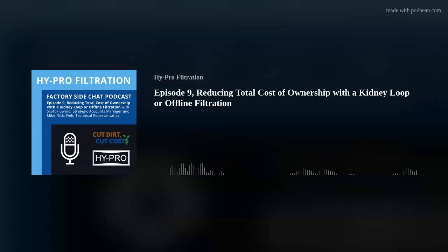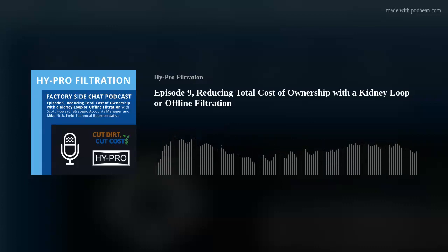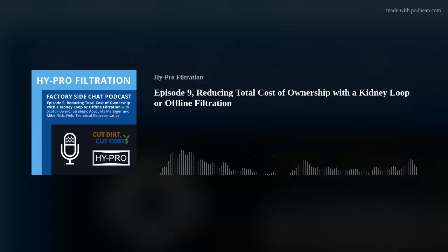But another benefit from that is because the kidney loop is online and operating, the inline filters, which are routinely the high collapse filter elements that are protecting a very sensitive component downstream, those are the most expensive filter elements in the system. High collapse means more material to manufacture. More material to manufacture means a higher buy price. So if we can make those filter elements last longer, that's a direct effect on total cost of ownership as well. And the other benefit with a kidney loop is we can shut it down and change the filter element without having to shut down the system. And so that allows production to continue and minimizes downtime for the system that it's attached to.